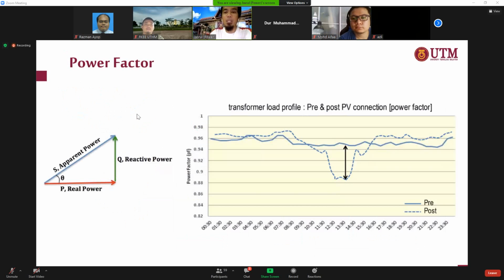All right, and last but not least, this is the most critical part, the most significant impact that we can see when we inject PV into the system. The PV can cause a power factor problem. This is the real power factor measurement taken from the TNB transformer. The blue line is before we have a PV, and the dotted line is when we have a PV. You can see here, starting from around 10:30 until 4:30, it will drop significantly. Previously the power factor was around 0.96, but now it is less than 0.9 during the noon.